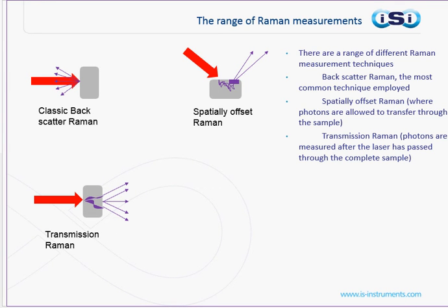Another common method is transmission Raman. In transmission Raman, the laser light is fired from one side and the Raman photons are measured from the opposite side of the sample, after the photons have travelled through the sample. This gives you a complete bulk measurement of the sample, making it ideal for quality assurance applications. However, this technique requires quite high-sensitivity spectrometers to measure.